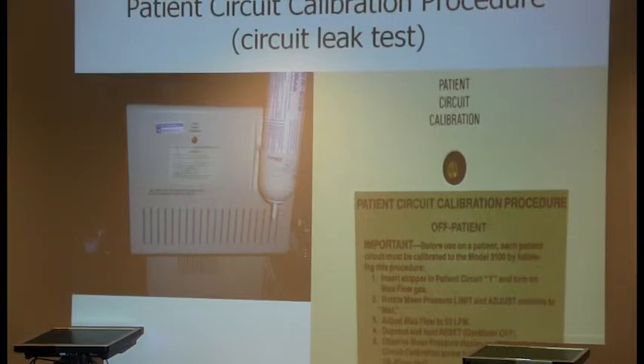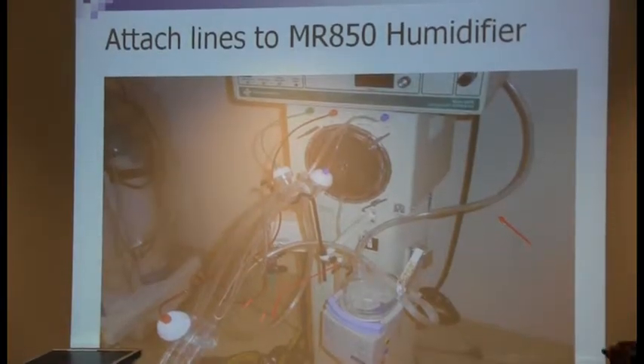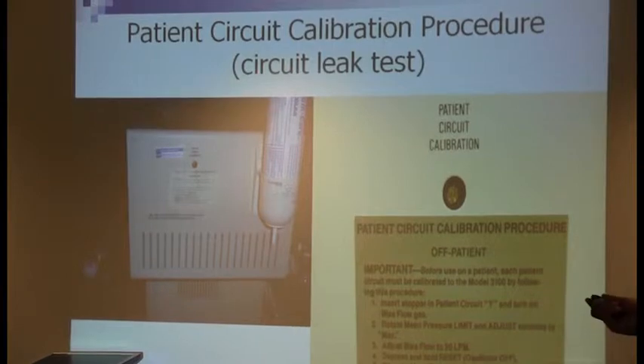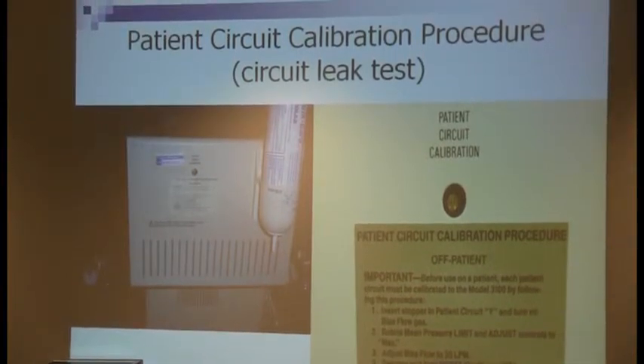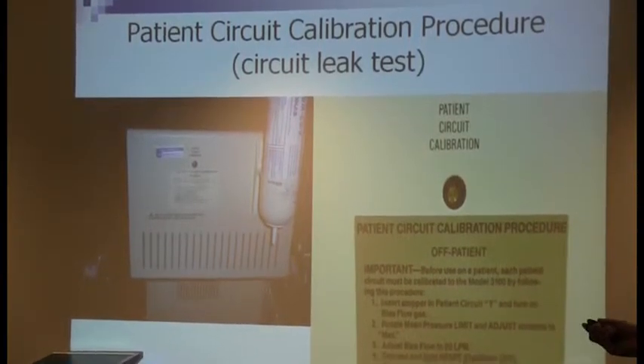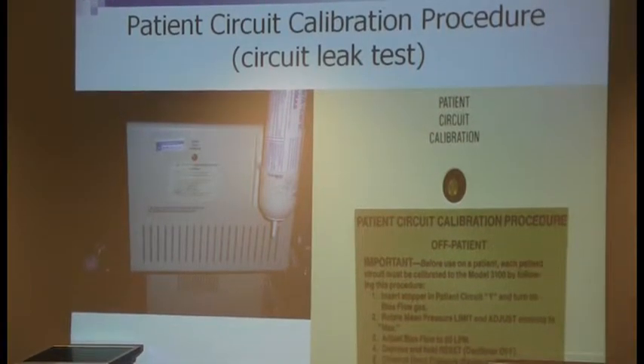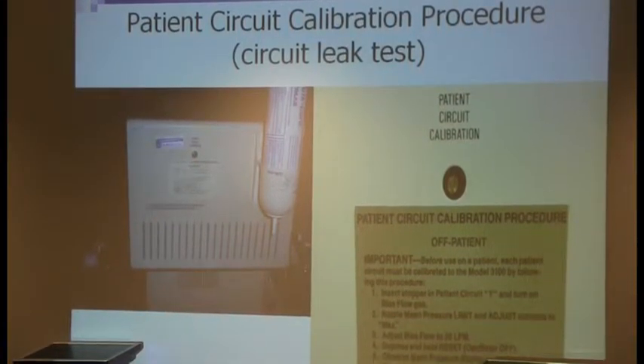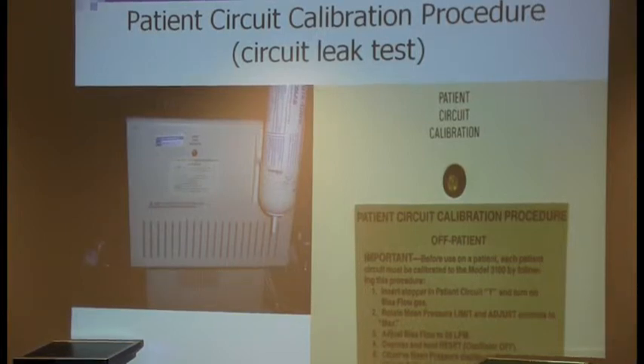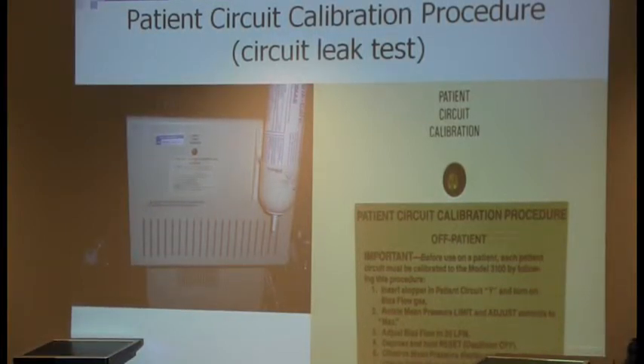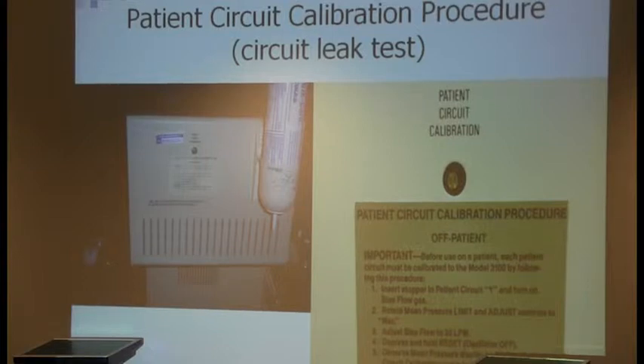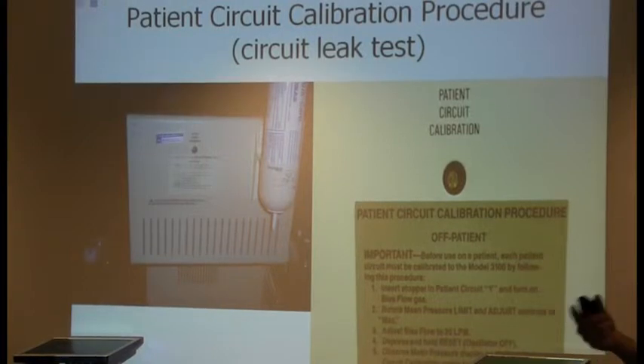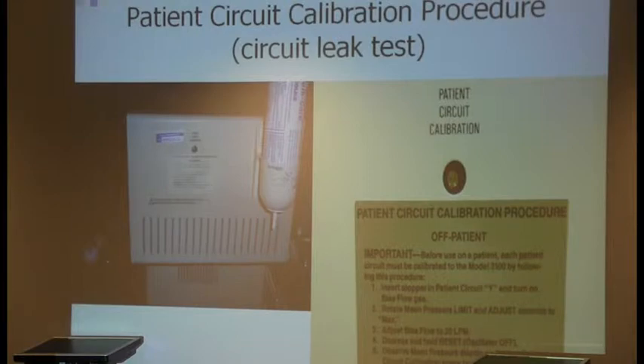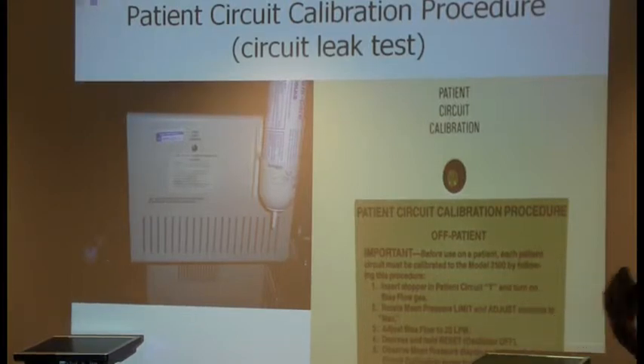All right. So after you got your circuit set up, now we need to do the patient circuit calibration test. Why we do this is to make sure that we have no leaks in the circuit. So when the question is asked, why do we do this procedure? It is to make sure that we have no major leaks in the circuit. Because if we have big leaks, then we're not going to be able to achieve the high mean airway pressures that we need. We're not going to be able to achieve the high amplitude settings that we need to get the patient to vibrate. So it's very, very important.